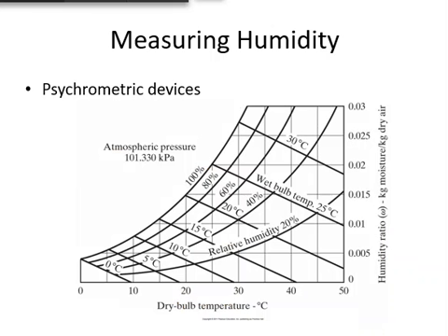The temperature of the wet bulb is dependent on several heat transfer processes. The sought-after effect is convective heat and mass transfer between the wet wick and the surrounding air. Unfortunately, there is also conduction heat transfer along the stem and radiation heat transfer to the surroundings.